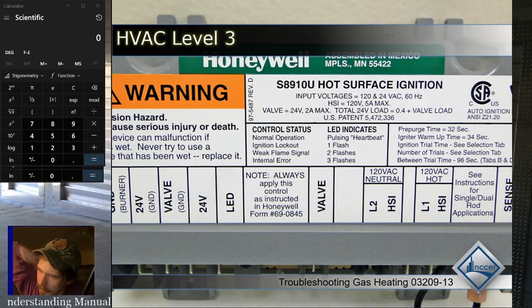There are a lot of systems that still have those check valves in them. Okay? So you'll know it's got a check valve when you see a pipe that goes around your TXV or around your piston. If you've got a pipe that goes around that metering device, there's a check valve in that pipe. And usually it just looks like a slightly bigger section of copper pipe. They're usually spun closed copper check valves.